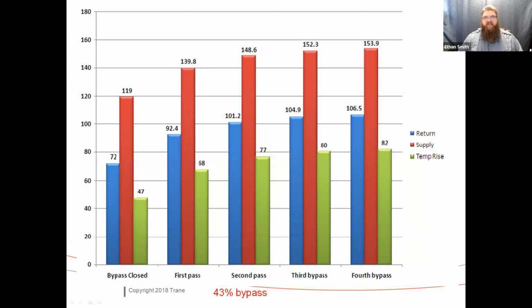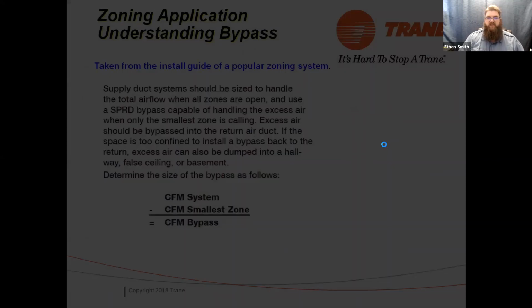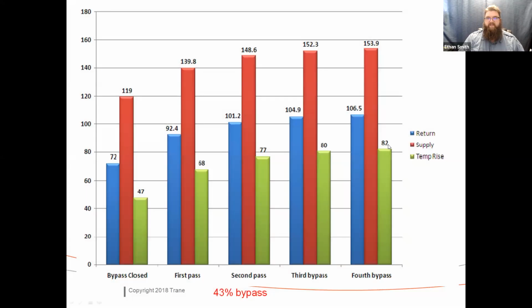So now we close that second zone. Now I'm at a 43% bypass. You think my furnace is going to operate very long at an 82-degree temperature rise across it? No. No, no way. Absolutely not. I'm hitting the limit. Okay. So this furnace is going to cycle on the limit. Eventually the limit will wear out. And eventually the heat exchanger will wear out.